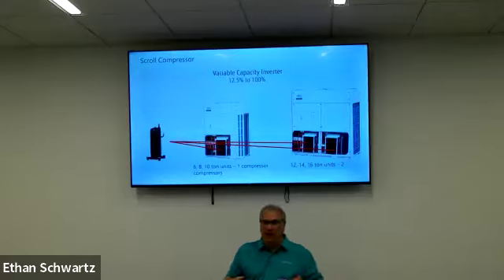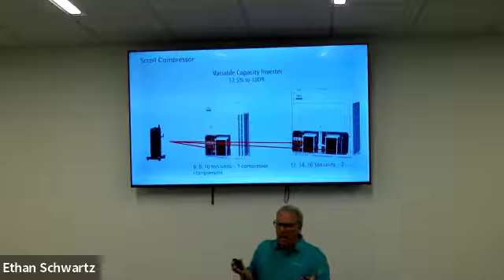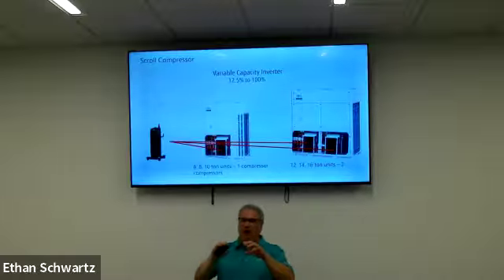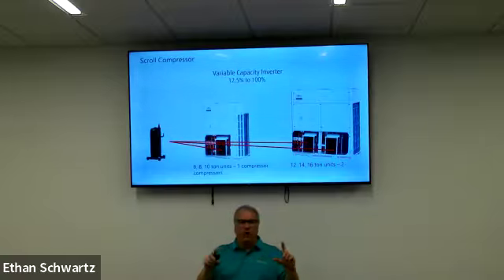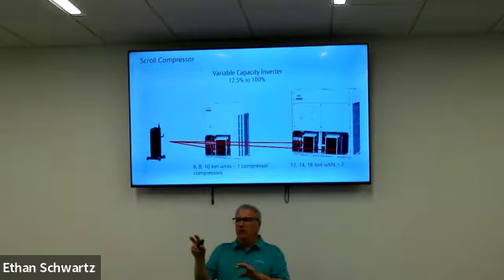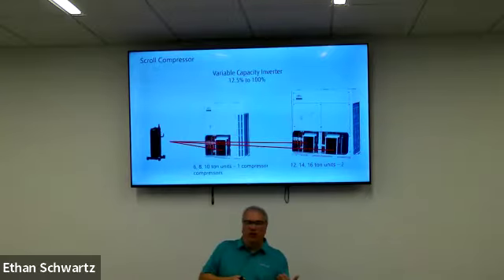Happy guests. When I go to a hotel, I want to be happy. I want a clean room and a comfortable room. If they have more of those rooms on fewer indoor units or on one circuit, and you have an issue with that circuit, what happens? The whole hotel goes down. If you do several or a few, break it up, maybe a third goes down. Are they really occupied to 100% occupancy at all times?